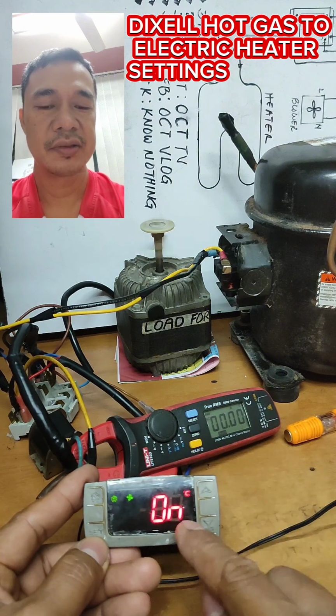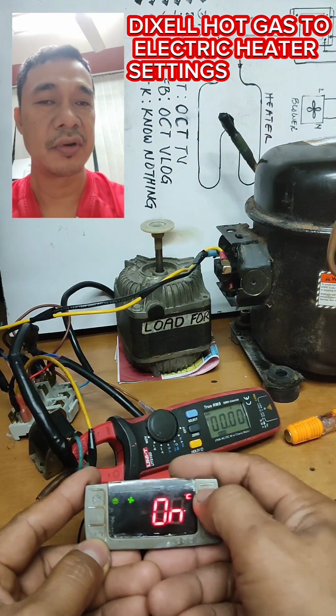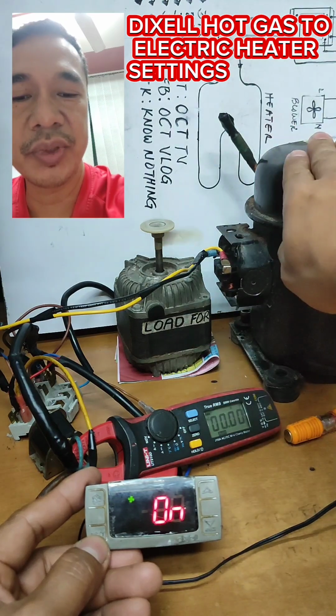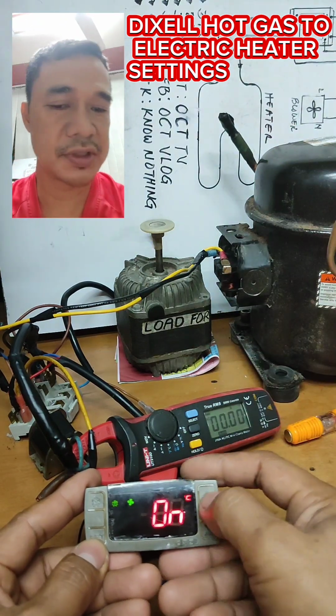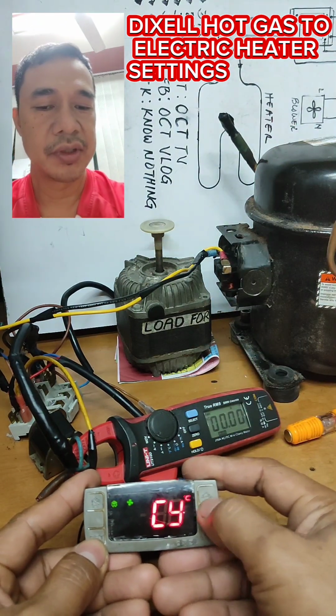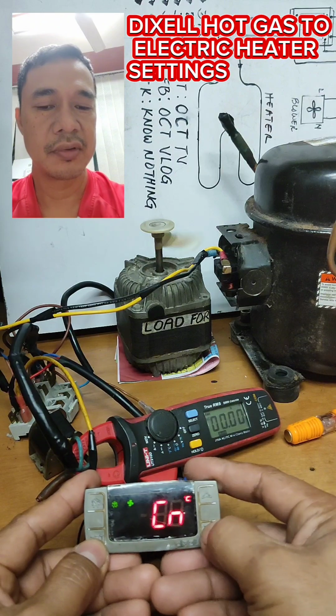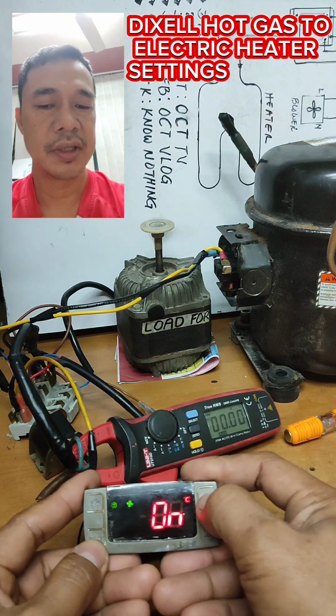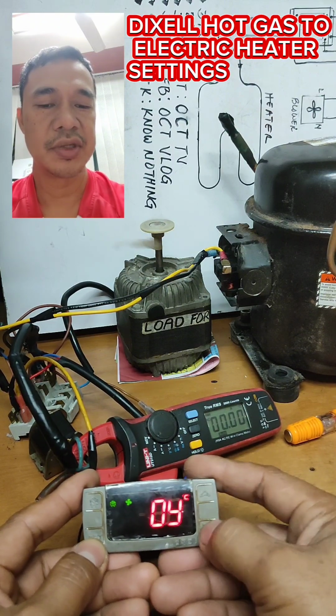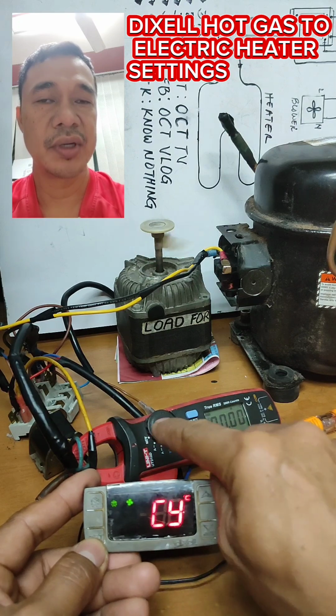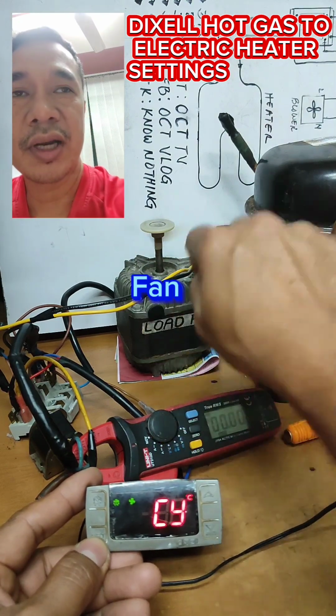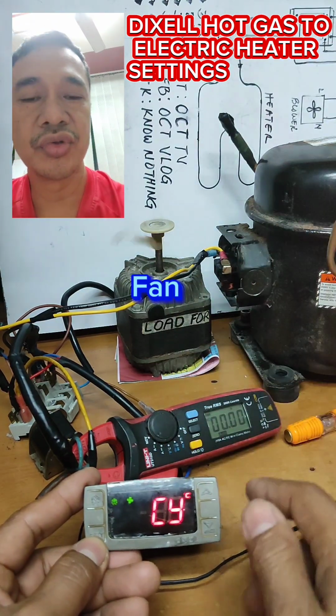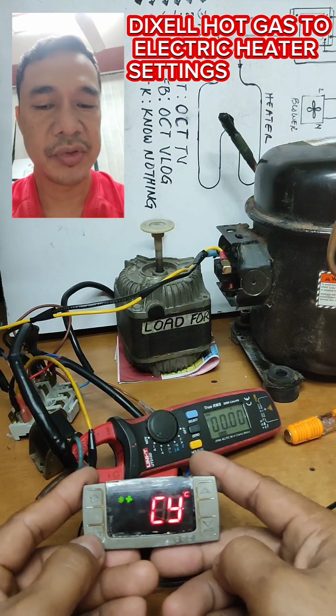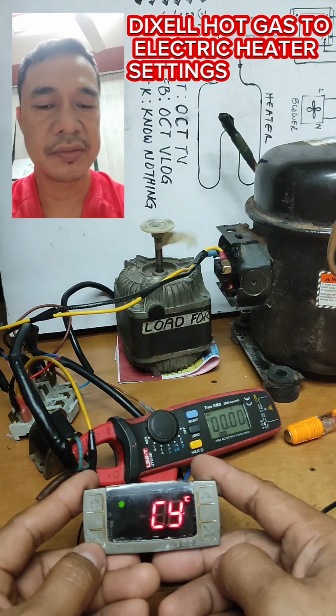Preset stands for evaporator fan runs with compressor, off during defrost. We're going to select CY here: evaporator runs with compressor on during defrost, and we're going to press the set button here.